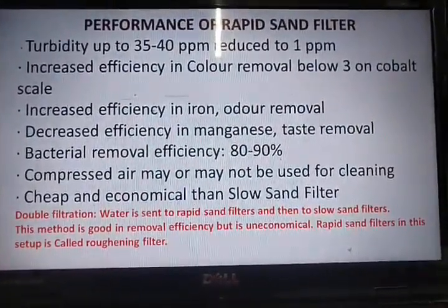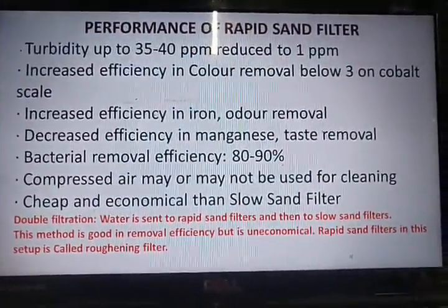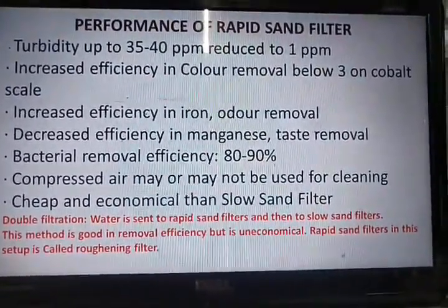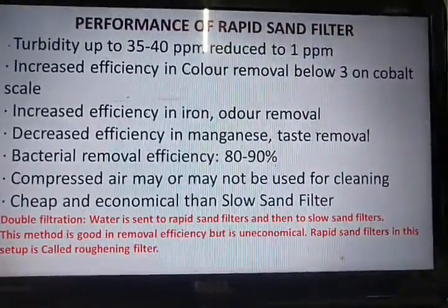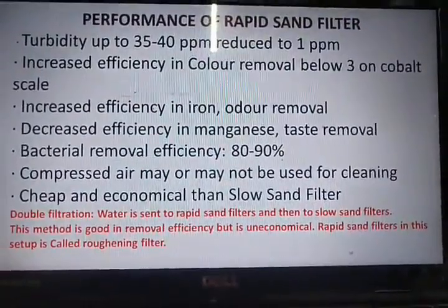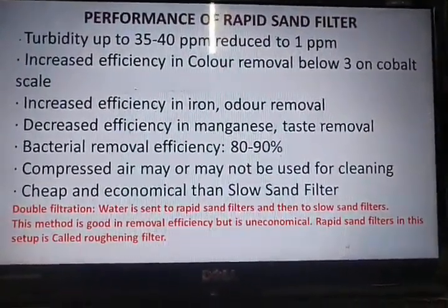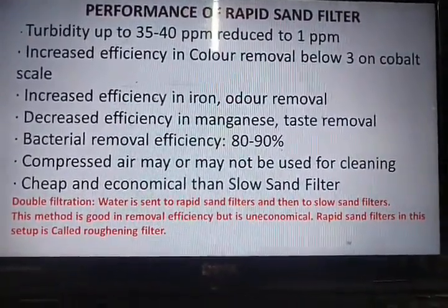Then performance of rapid sand filter. Okay, so like I told you, the turbidity will be reduced here greatly from 30 to 40 ppm up to 1 ppm. Okay, and it also removes color as well.